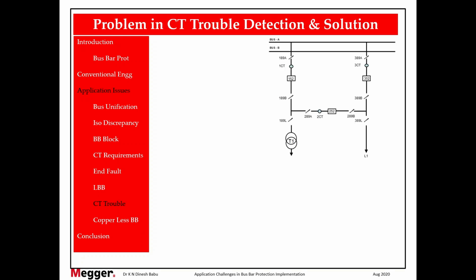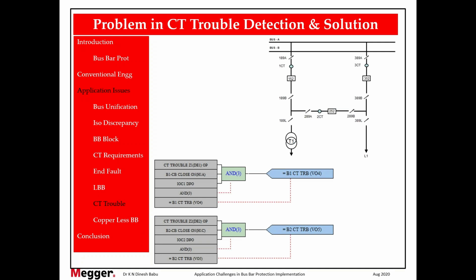The third example is a 1.5 breaker arrangement. This is similar to single bus bar. So the same logic goes in, but it goes 2 times. CT trouble in the respective zone, along with that breaker close condition, and undercurrent for each zone. And we repeat it. This is also evident from the logic shown over here.